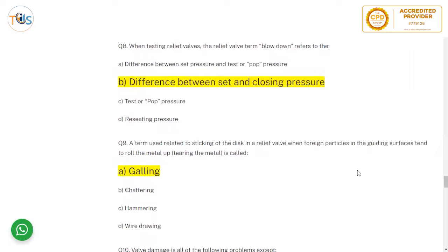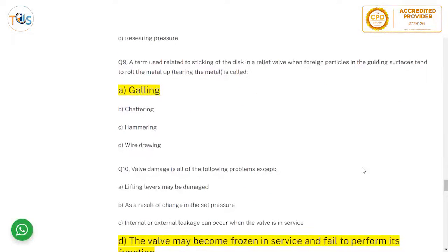When testing relief valves, the term 'blowdown' refers to the difference between the set pressure and the closing pressure — that is, once the valve has opened, blowdown refers to the pressure at which it closes again. The term for sticking of the disc in the relief valve when foreign particles in the guiding surfaces tend to roll up the metal is called galling.